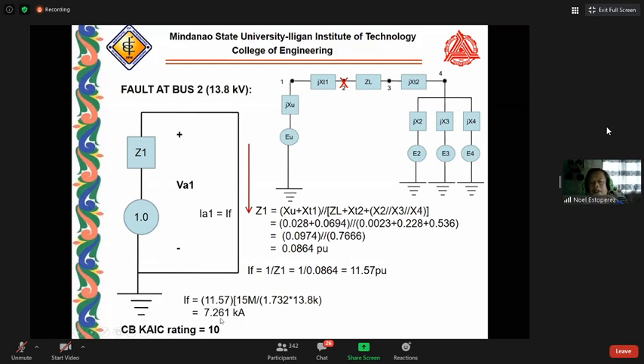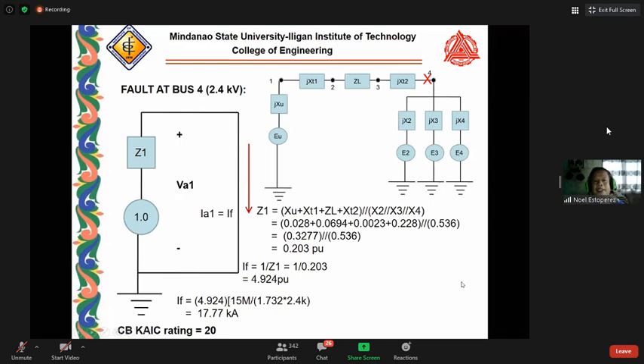So we have fault current of 7.261 kiloamperes. Maybe we can select a KAIC rating of 10. So that is for our fault at bus 2.